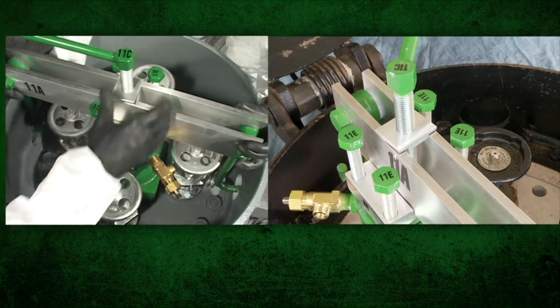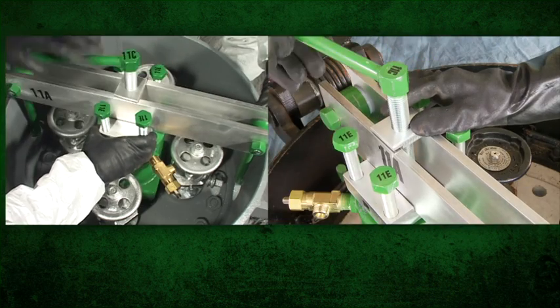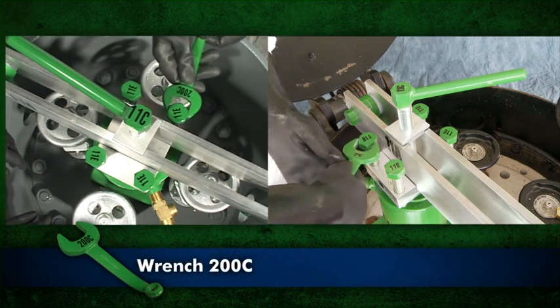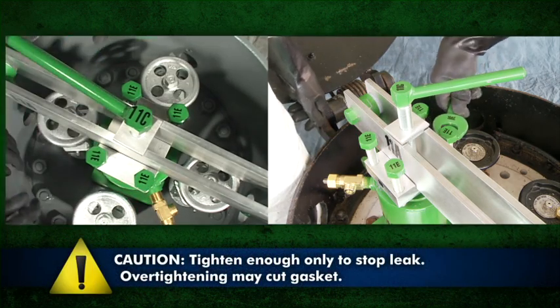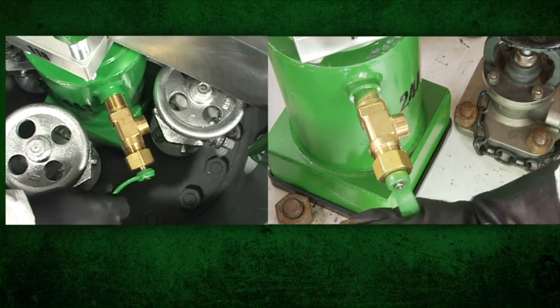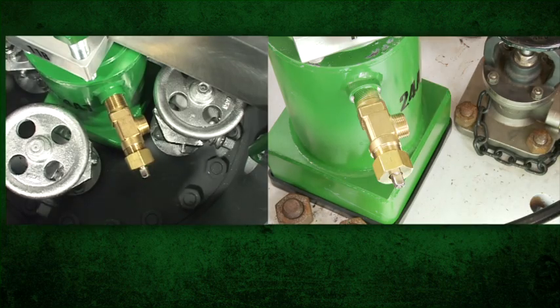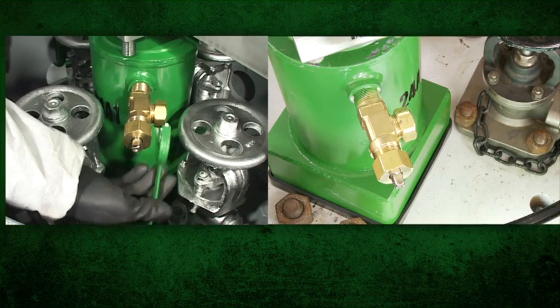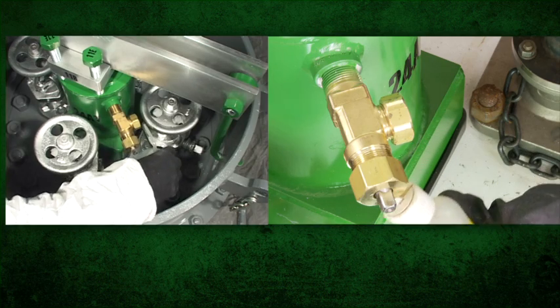Center screw 11C over Hood 24A1 and tighten screw 11C, forcing Hood 24A1 and gasket 24BMV against the pressure plate. In an alternating pattern, tighten screws 11E in block 11B using wrench 200C, forcing Hood 24A1 and gasket 24BMV against the pressure plate. Tighten only enough to stop the leak — overtightening may cut the gasket. Close vent valve 24V on Hood 24A1 using wrench 200C. Replace the vent valve 24V outlet cap. Test for leaks immediately after installation and at regular intervals if the capping is to be kept in place for an extended period.